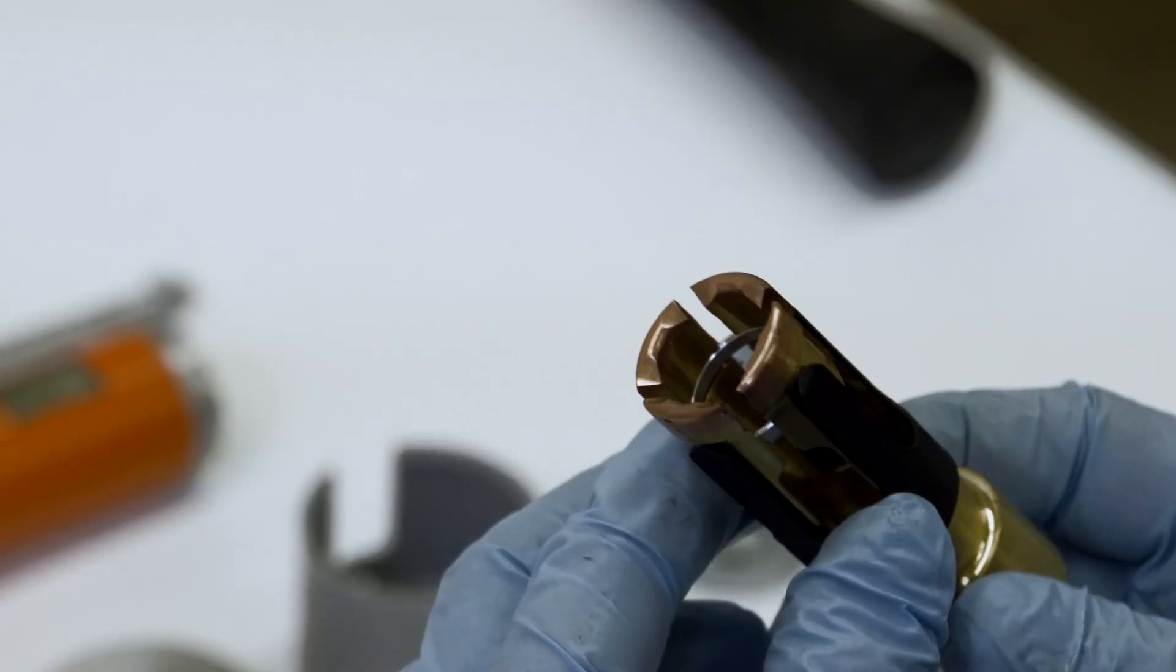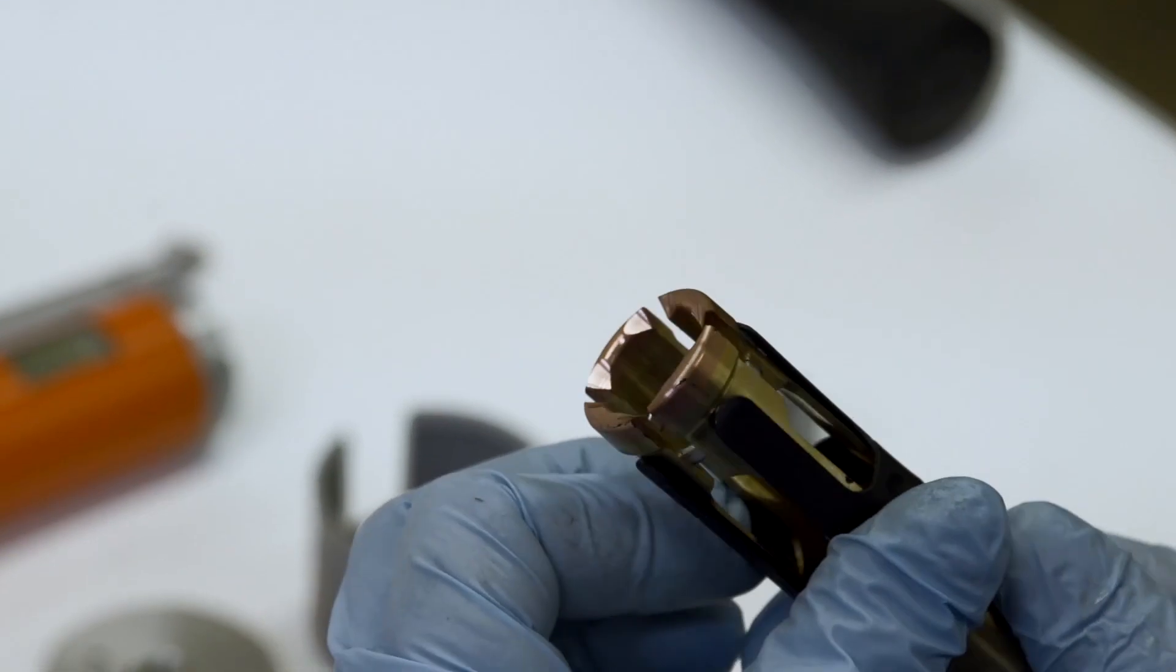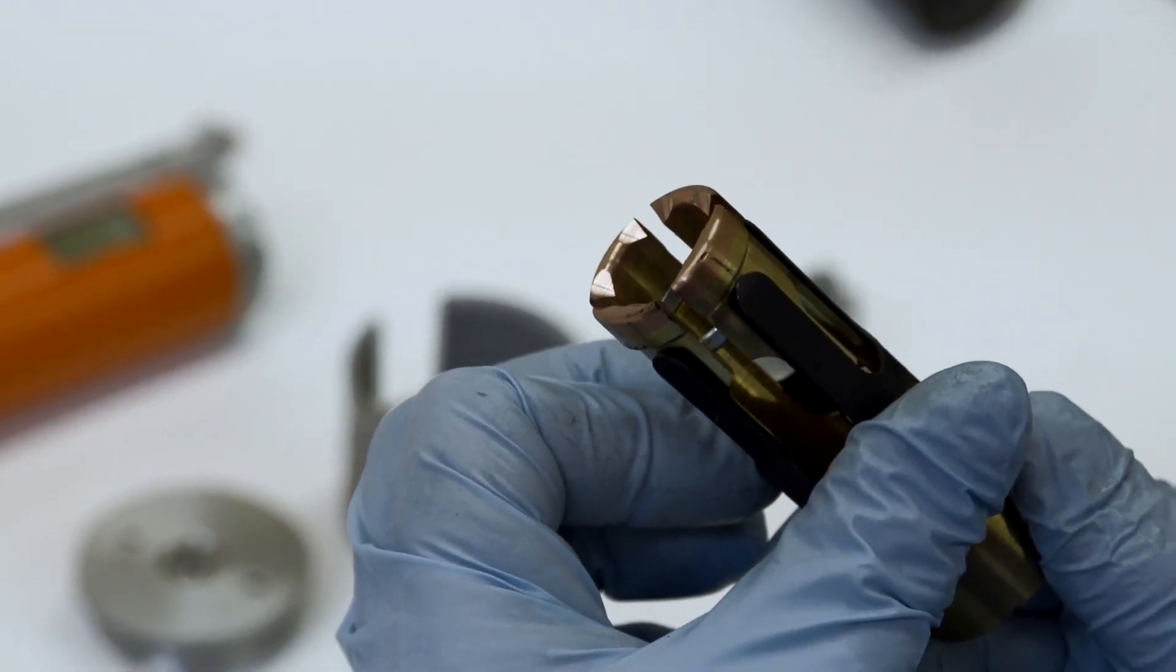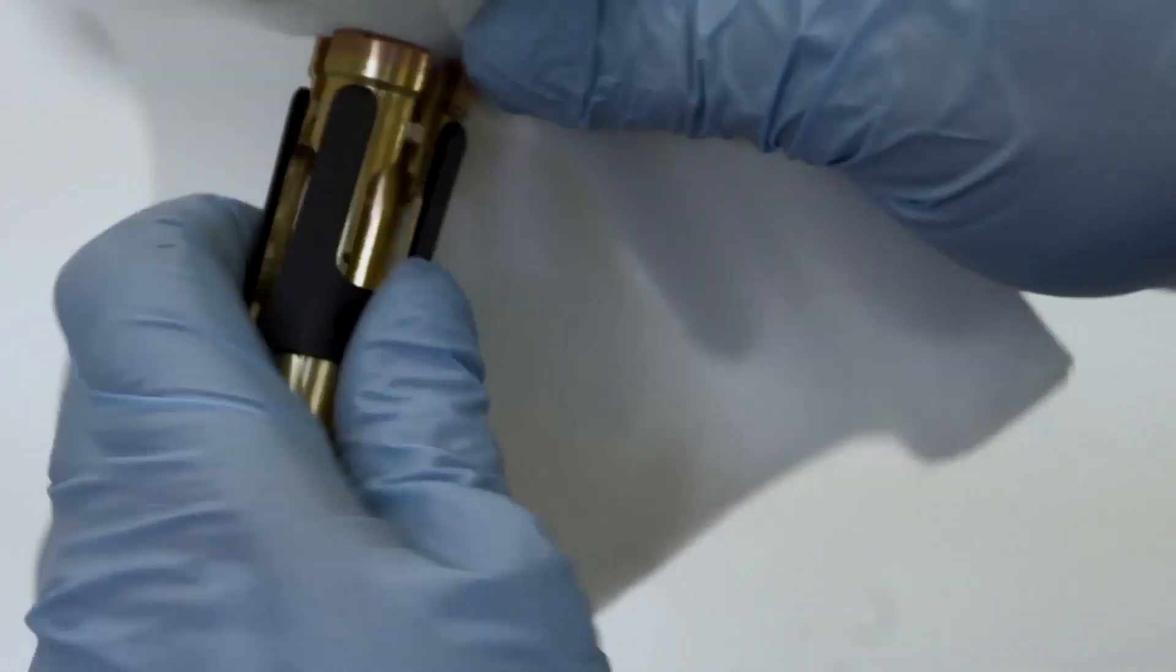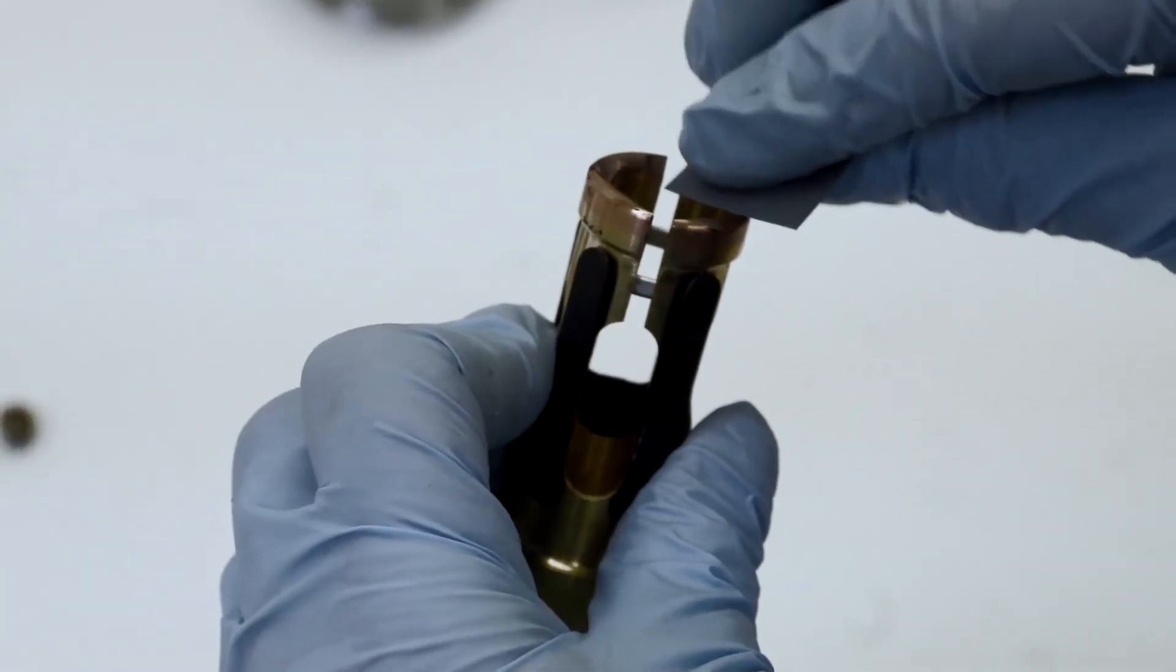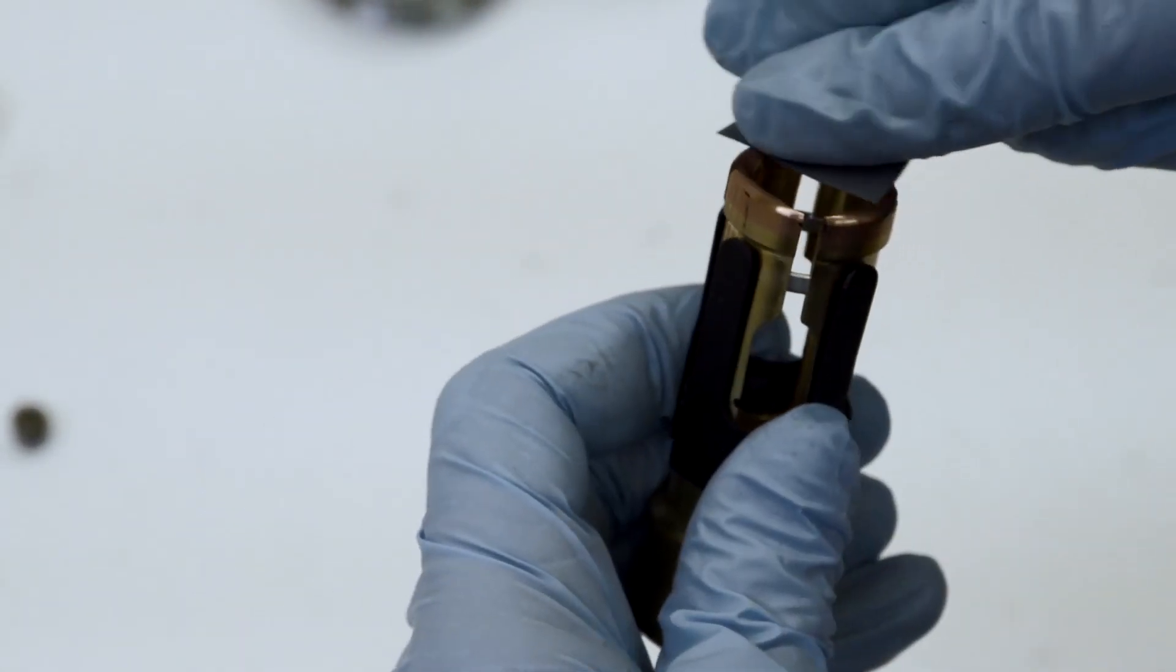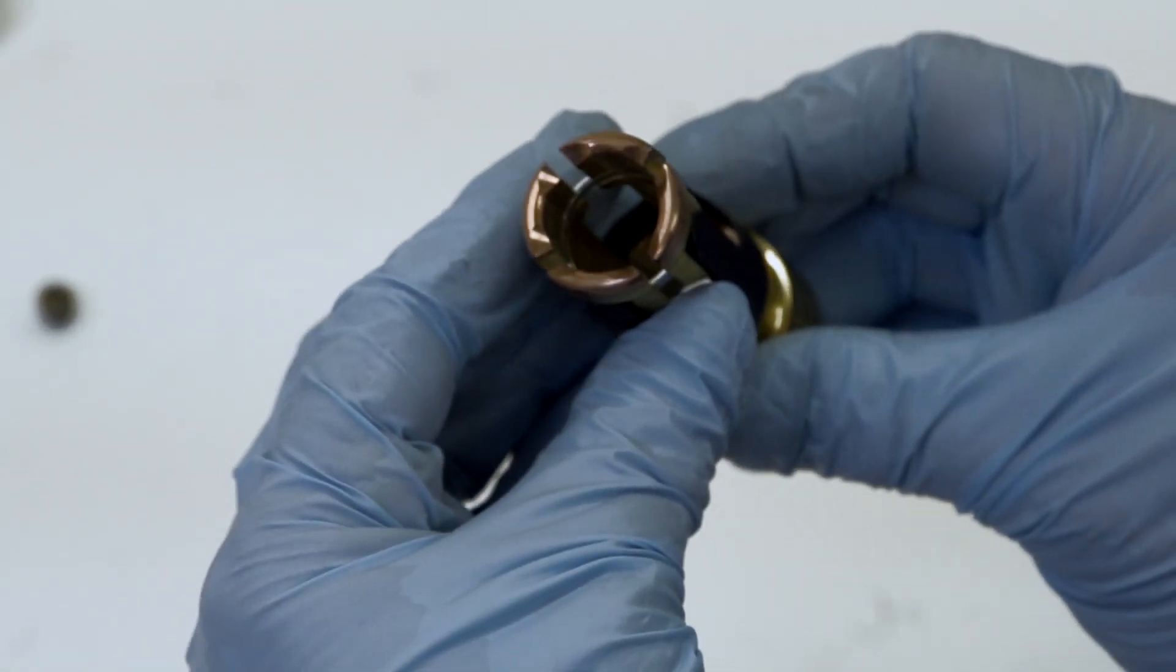Next we'll look at the stationary contact assembly. Remove any carbon deposits using water and a liquid abrasive type household cleanser. Thoroughly rinse and dry the assembly immediately after cleaning. Polish with an emery cloth if necessary, but avoid filing which could change the dimensions of the assembly.